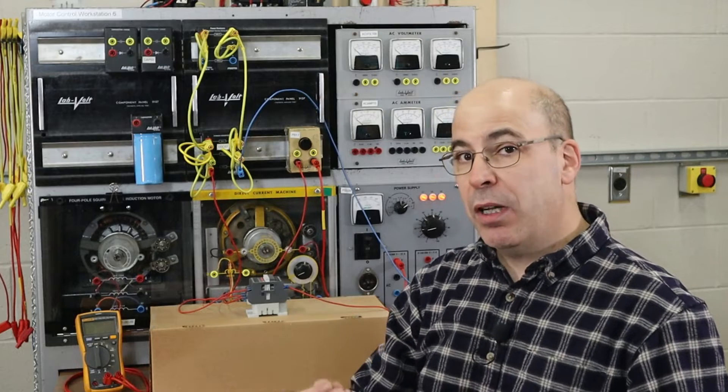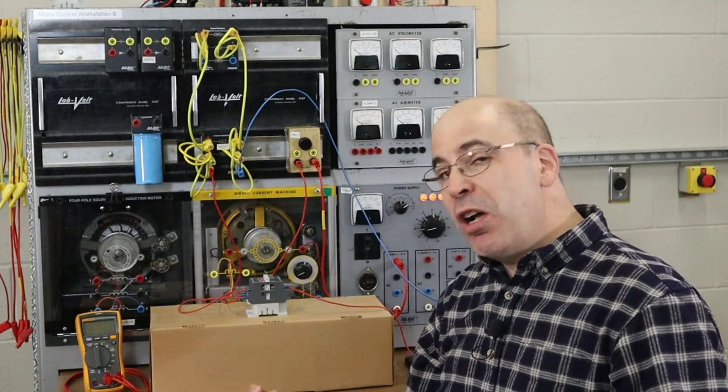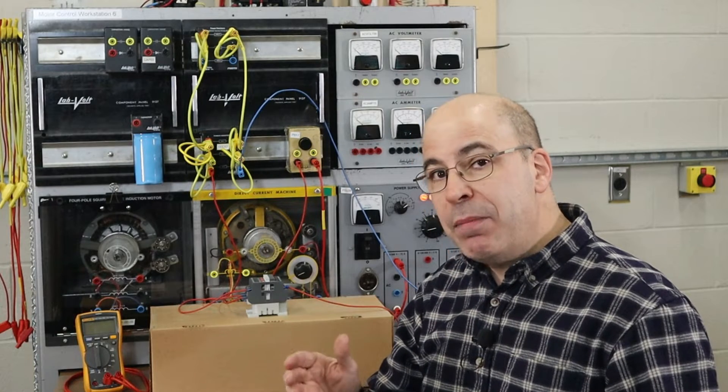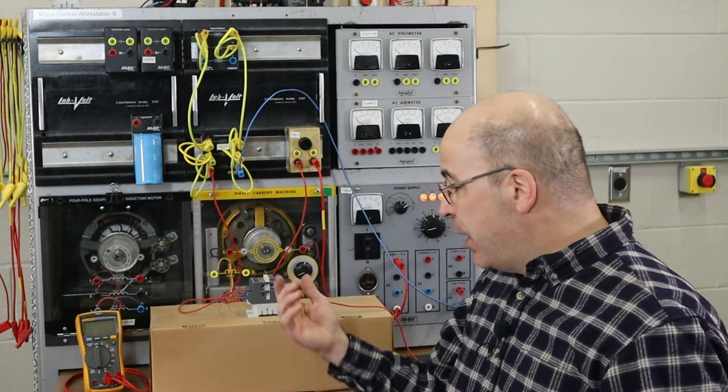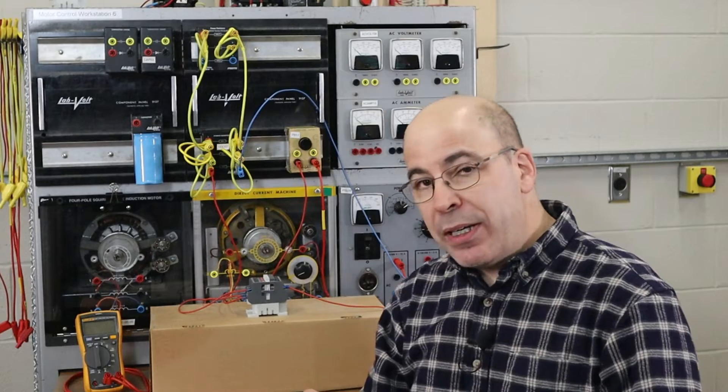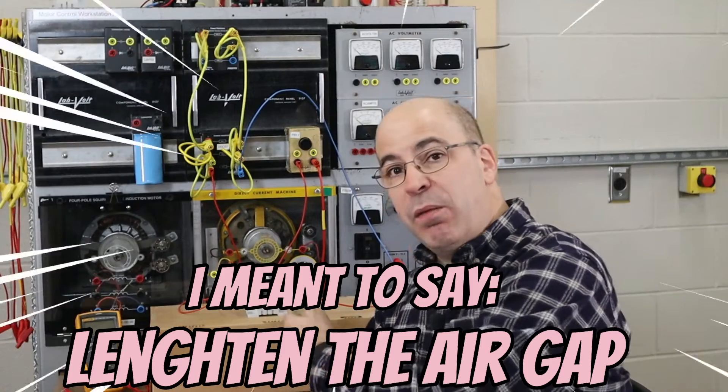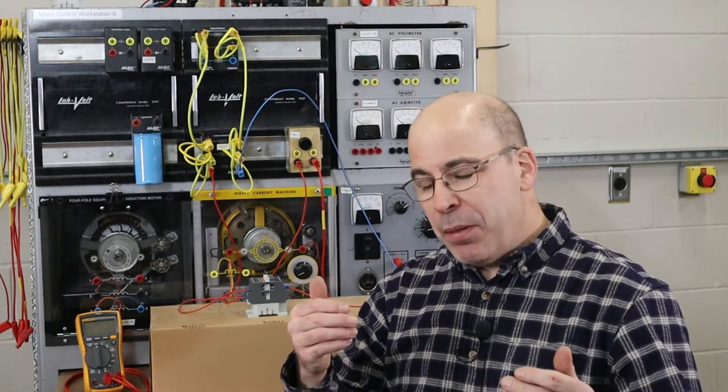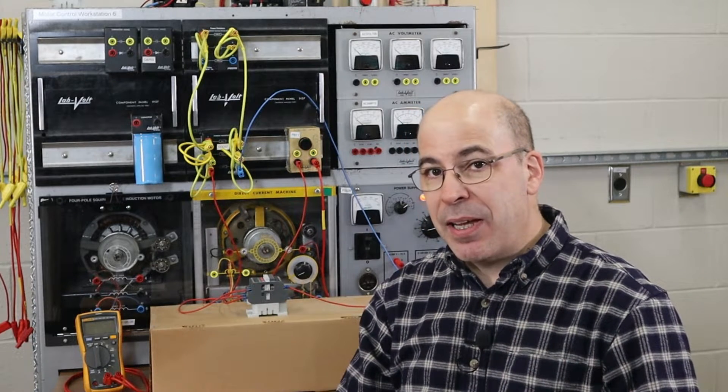Yes, there is still a tangible arc, but it is not sustained. That is one technique that can be used effectively to help mitigate arcing. We can lengthen the contact material. I did that by switching devices, but we could also put two contacts in series with one another. But you're going to have some limited success.